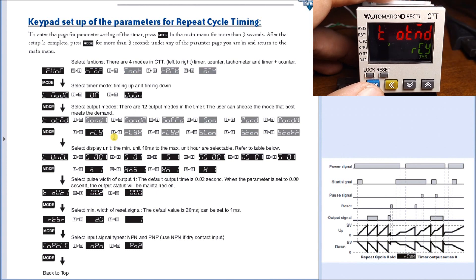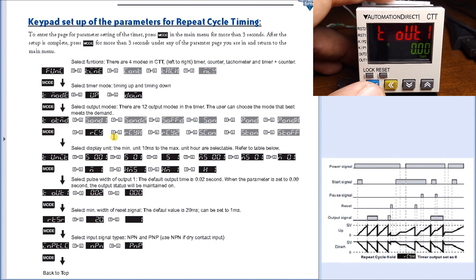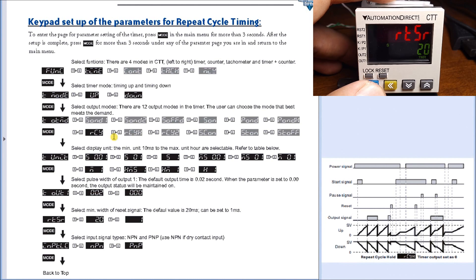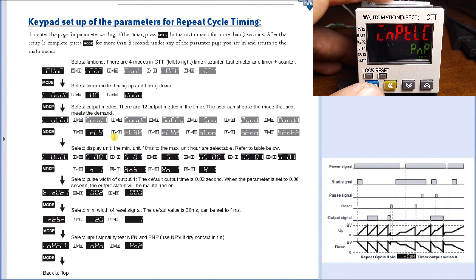And it changes it to that cycle. Then what we'll do is hit the mode once again. There's our time units, which is set for 0.1 of a second. Then we have our output, which is set for 0, which is maintained output. Time mode again, our reset is 20 milliseconds. And then we have PNP as our input type selected.